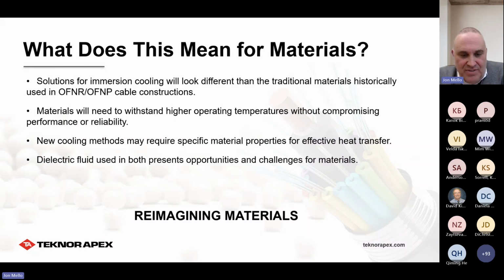If you're now going to have cables living in a fully submerged environment, what does that mean for performance? What does it mean as far as swelling of the material or cracking? Will the cable crack? Will the material absorb so much liquid that it'll crack and expose the core? Can't have that. With a submerged cable, will something in the formulation leach out into the cooling material and run the risk of potentially damaging very expensive, sensitive electronic equipment? Again, we're looking at all these requirements now, and what does that mean for material solutions moving forward? We'll talk about this as we move into these different slides.